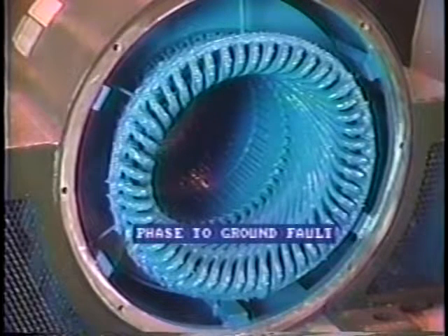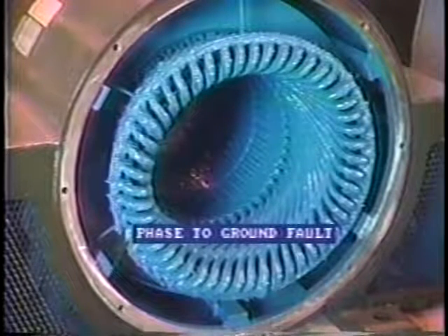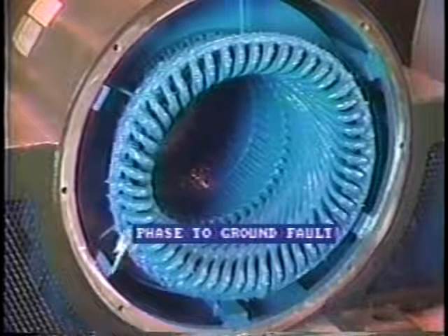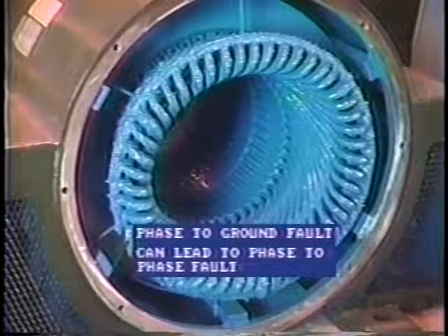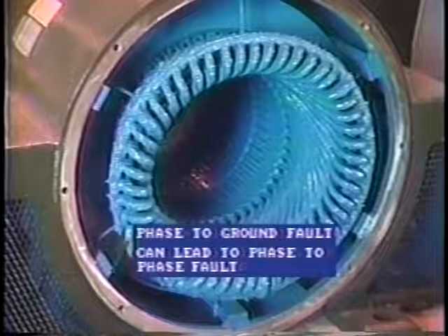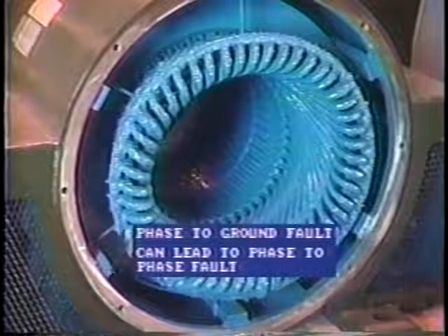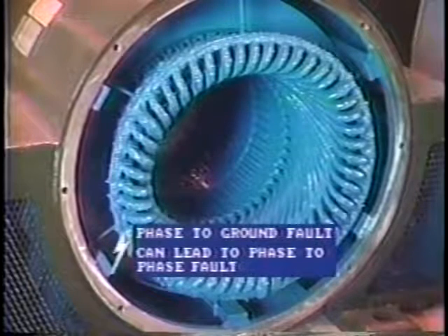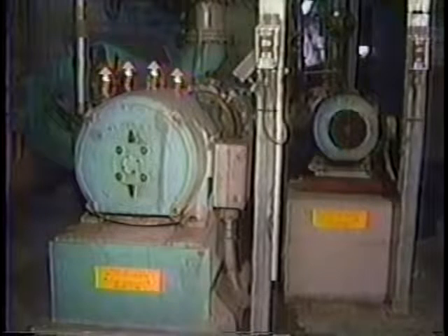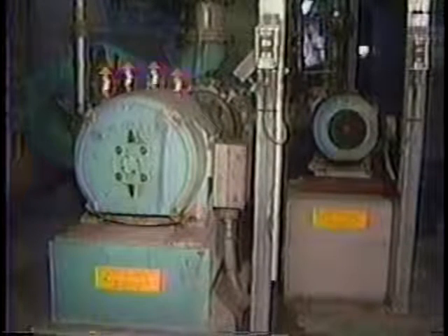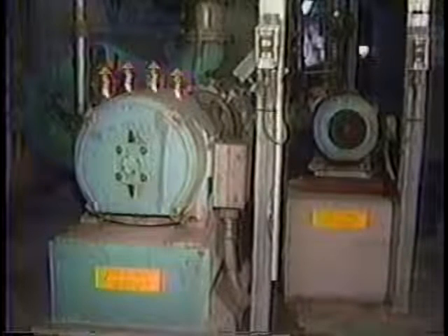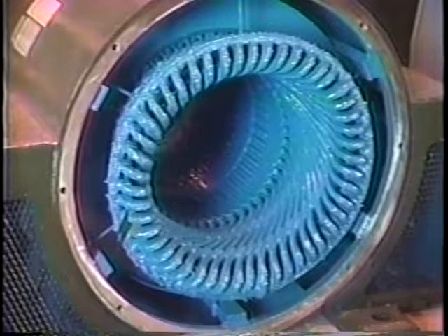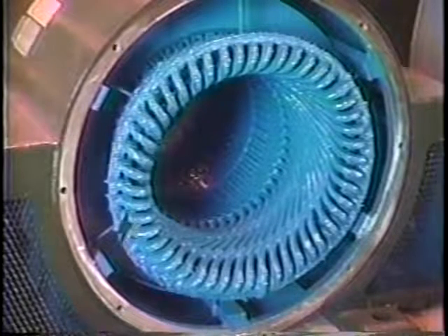Now, let's look at the various types of faults that can occur on a motor. The first that comes to mind is insulation failure on the stator windings. The consequence is a phase-to-ground fault, as the insulated conductors are fitted tightly into the slots of the iron core. In many cases, this fault also leads to a phase-to-phase short circuit in addition to the ground. We'll be looking at protection schemes for fault conditions soon. A more common problem of the motor is overheating, which may go unnoticed over a period of time. Overheating leads to deterioration and eventual failure of the insulation. This causes a short circuit between phases and to ground.